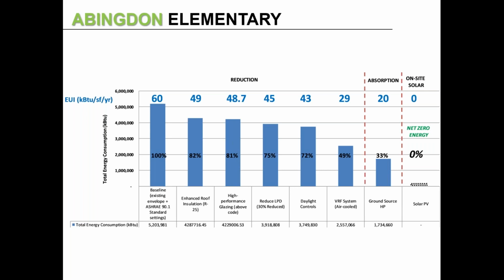Ultimately, we had a host of existing systems in the building—air handling units, rooftop units, etc.—that were relatively new. So the analysis was: is it worth replacing them? Keeping the existing equipment, we could get to an EUI of 40 kBTU per square foot per year. But ripping out all that relatively new equipment and swapping it for a VRF system would have gotten us to an EUI of 29. Ultimately, it was not worth it.